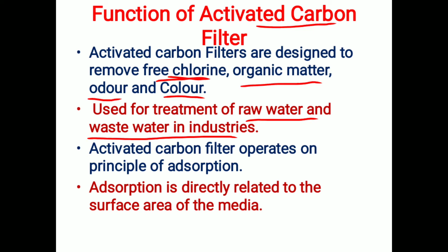For raw water treatment, it is used in the purified water plant and DM water plant that we use in thermal power plants, textile industries, and pharma industries. In the DM plant and purified water plant, we use this activated carbon filter as a pre-treatment. And in wastewater treatment, we use this ACF as a post treatment.